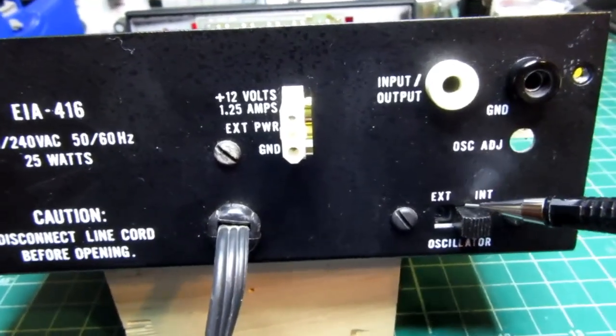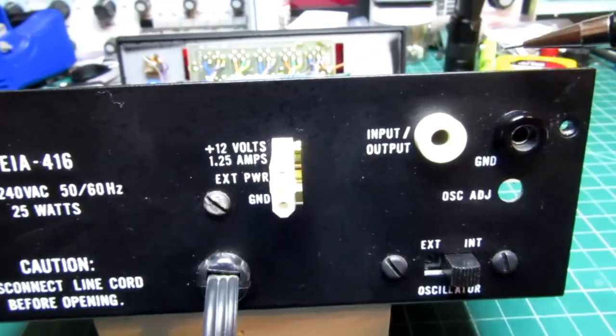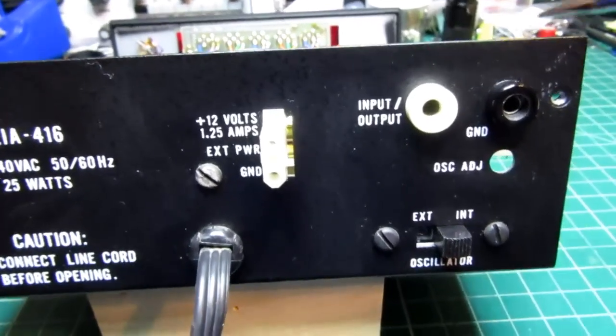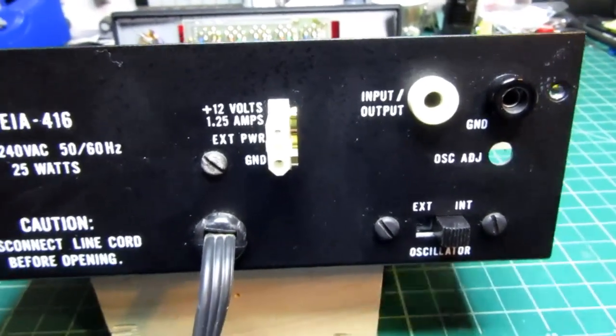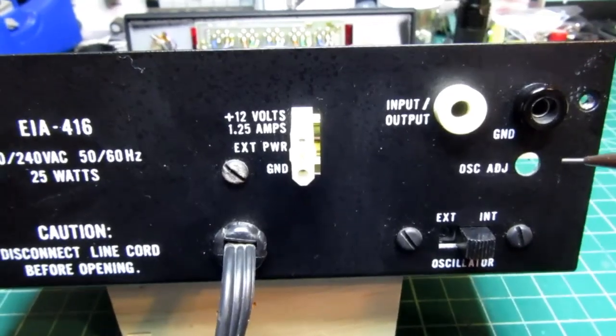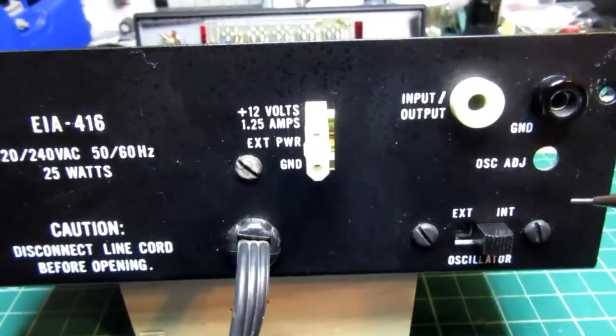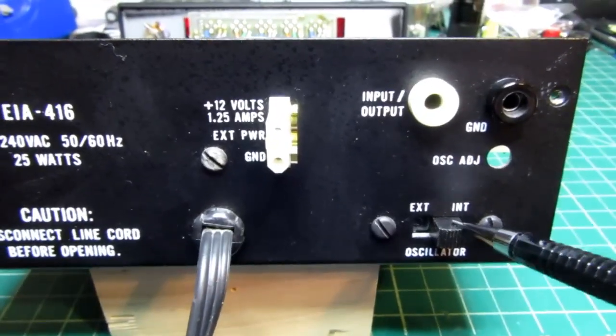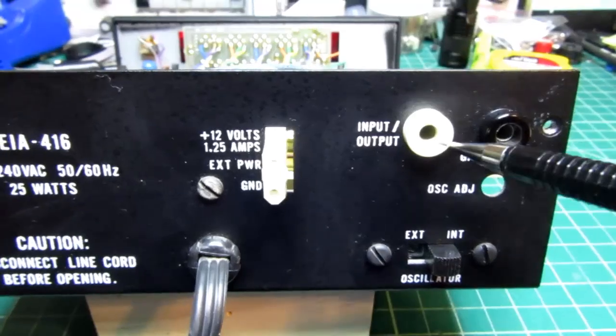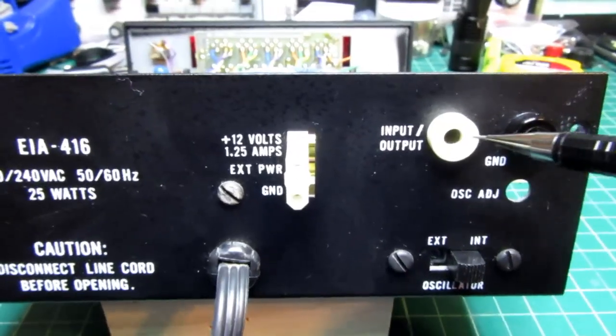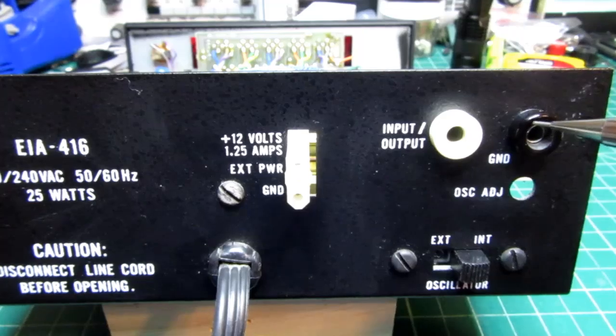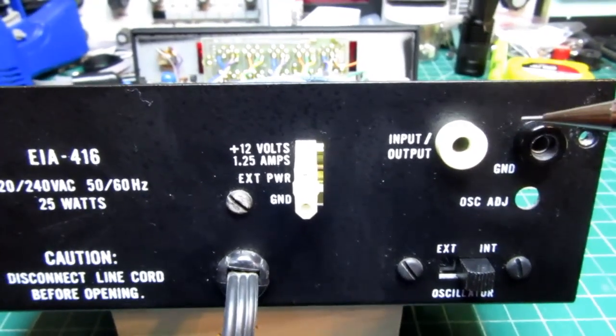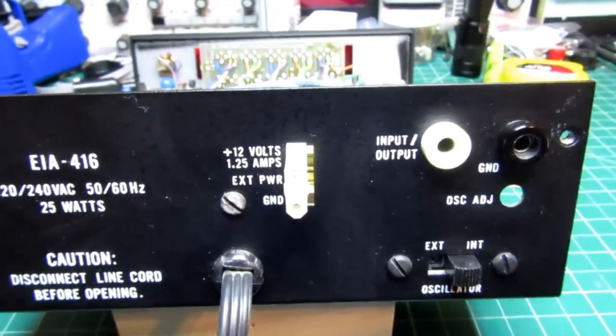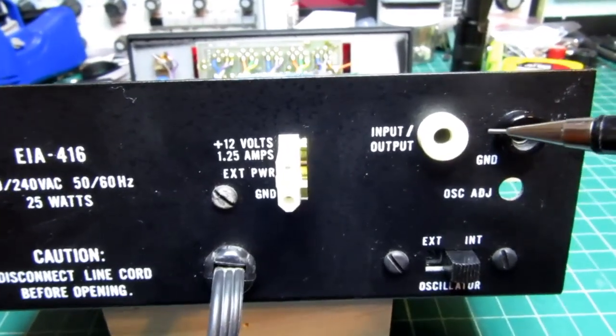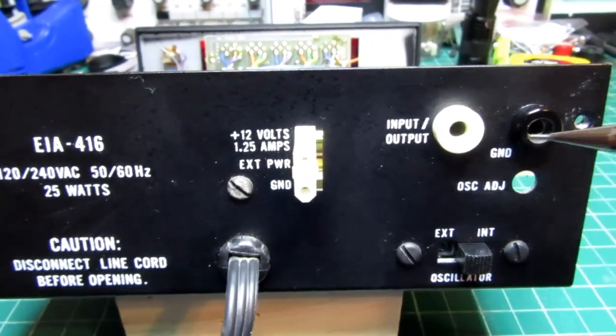In the external position, the internal crystal oscillator is disconnected from the master clock counter chain, and therefore the signal can be overdriven or overridden by the externally applied one. When you're in the internal clock mode, then that clock is applied to these as an output, so you can get external access to the internal 1 megahertz clock, which again is the 10 megahertz crystal oscillator divided by 10. If you're in the totalized mode instead of the frequency or period modes, then these jacks do something different.